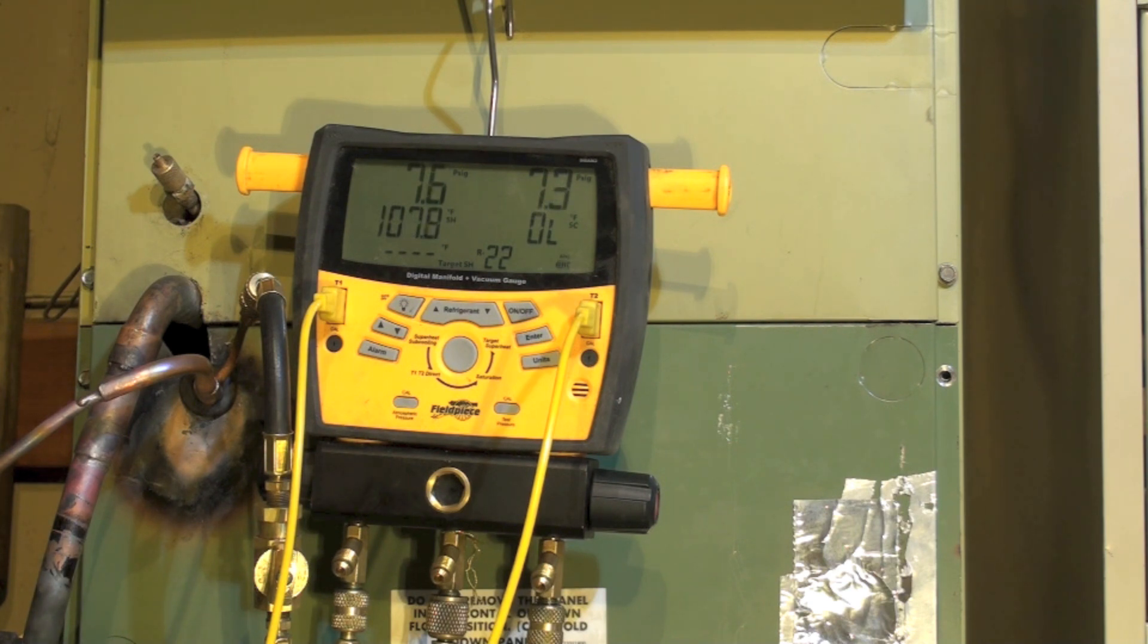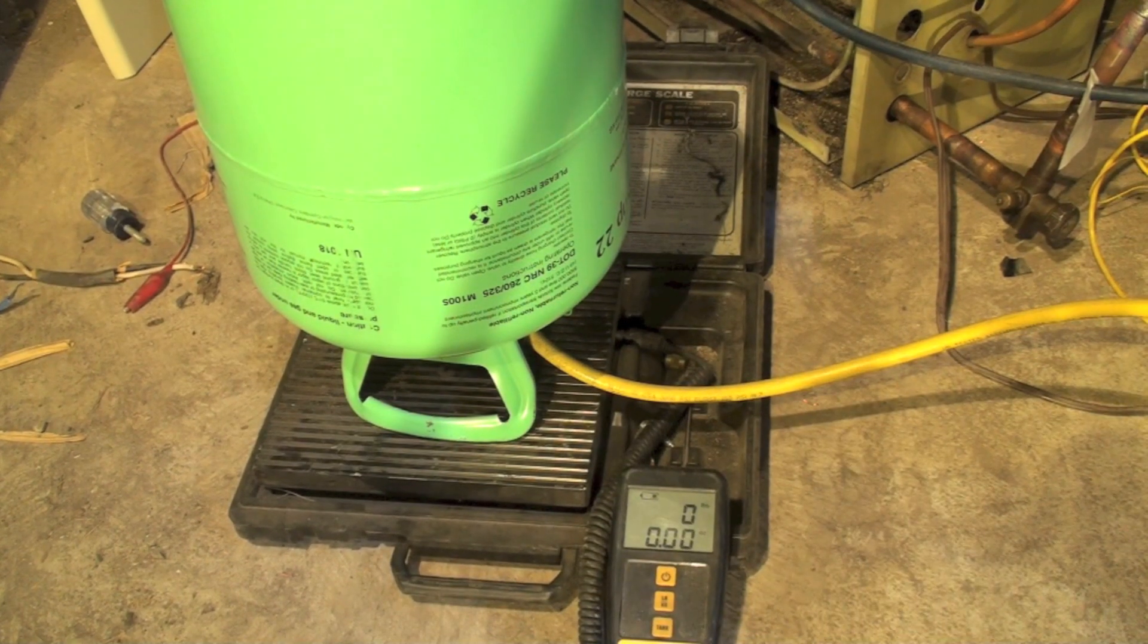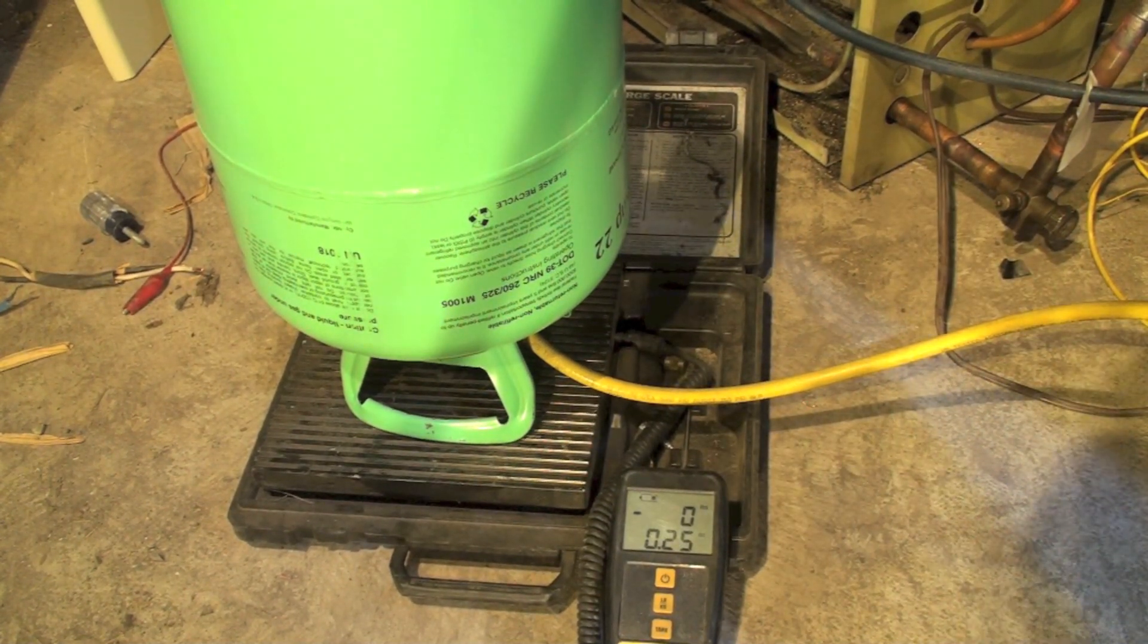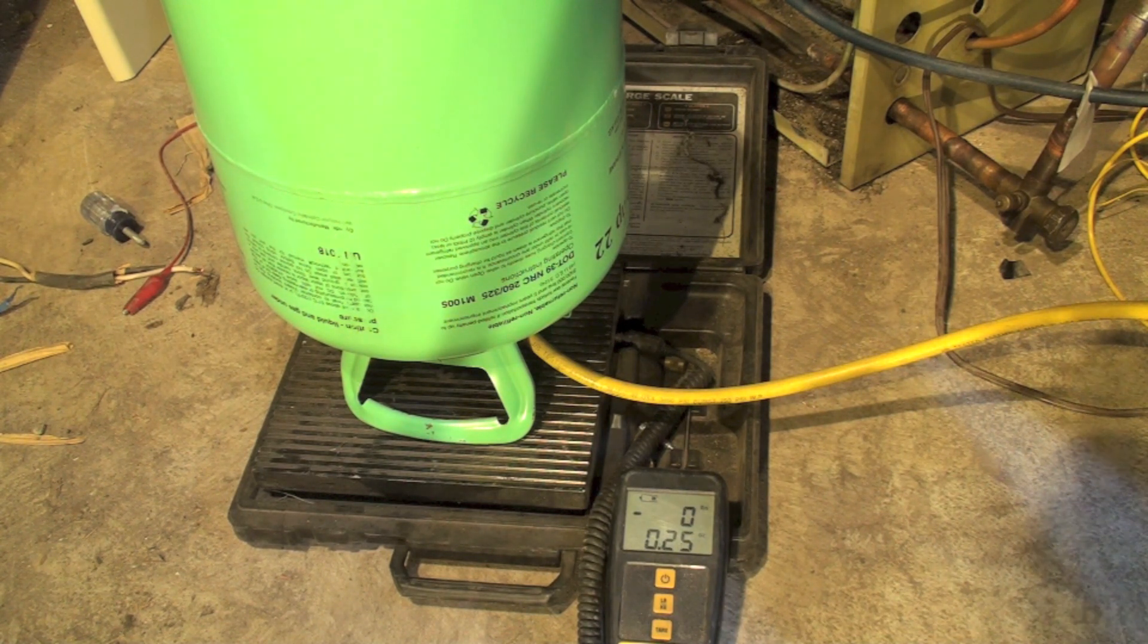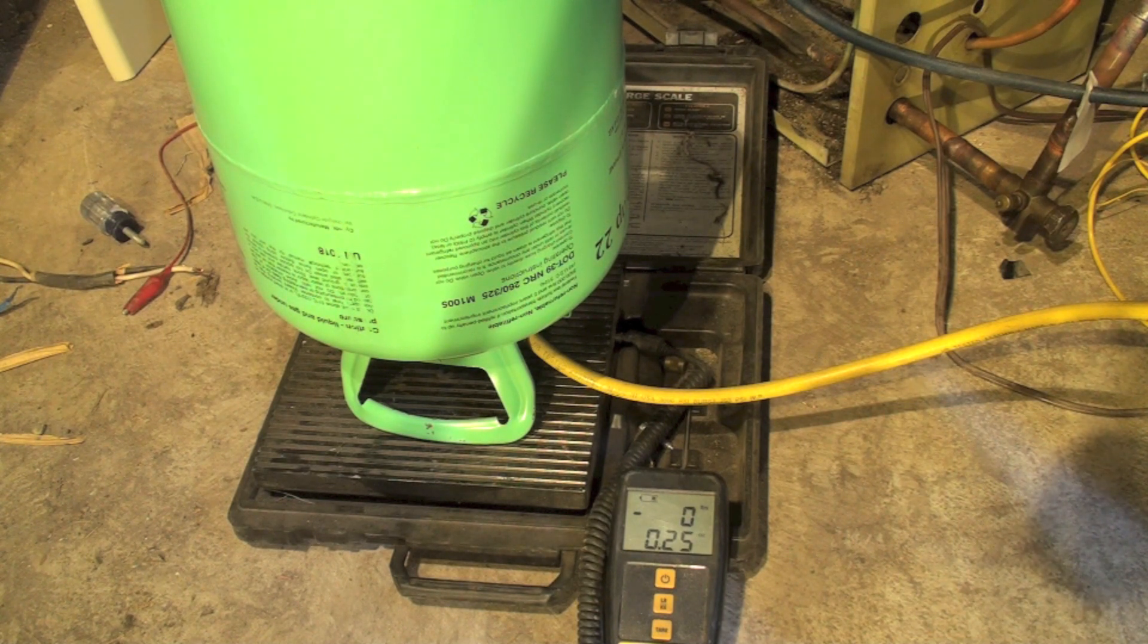Liquid can't go in the low side unless it's metered, but it can go in the high side. I'm going to show you where we're at with the cylinder. This is an R22 machine. If this was 410A or any other blend, it would have to go in liquid no matter what. We can do gas or liquid. We will start out with liquid.